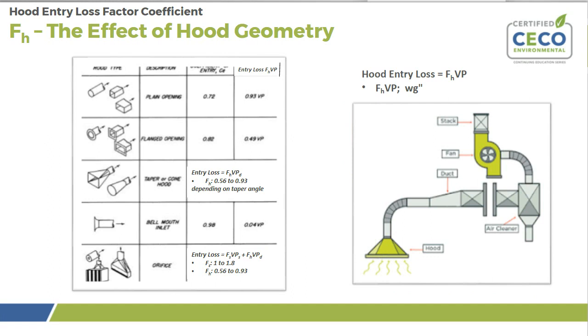Along with the distance from the source, another factor that affects the flow requirement is the geometry. And we see this effect with the hood entry coefficient F sub H. The reduction in velocity pressure associated with the hood losses is calculated as the product of the hood entry loss coefficient times the velocity pressure.